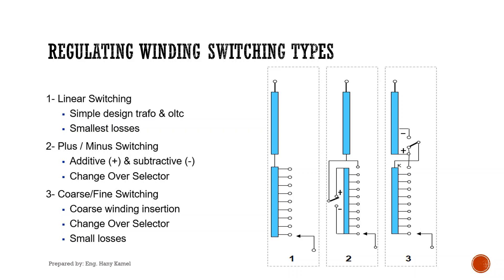For linear switching, it is mostly used when we have a fewer number of taps. In the case of distribution transformers, OCTC will be used, and in large distribution transformers, OLTC will be used depending on customer request. In case OLTC is used, no changeover selector will be available. For a larger number of taps, as in power transformers, reverse switching is commonly used. But sometimes, to meet customer requirements for load losses, the coarse-fine technique is used, as it gives lower DC resistance at the lowest tap.